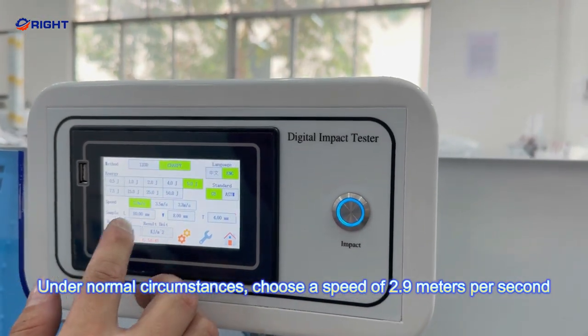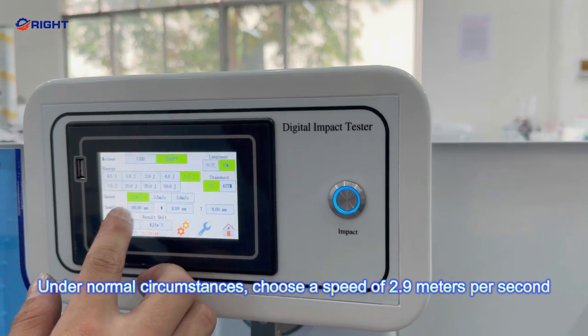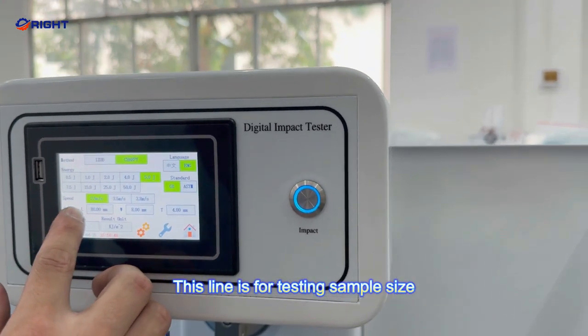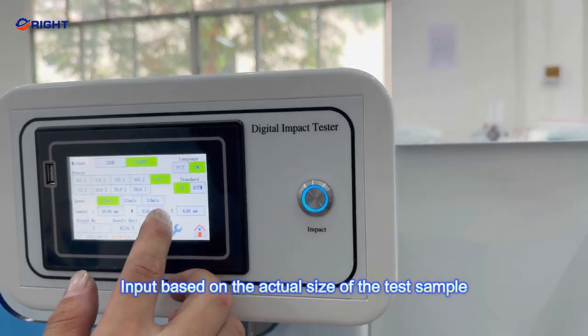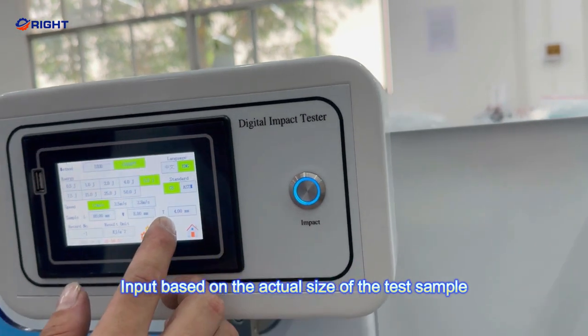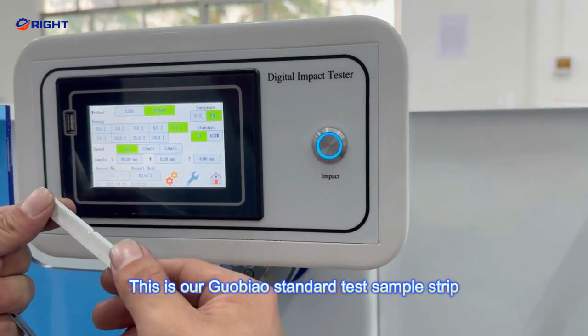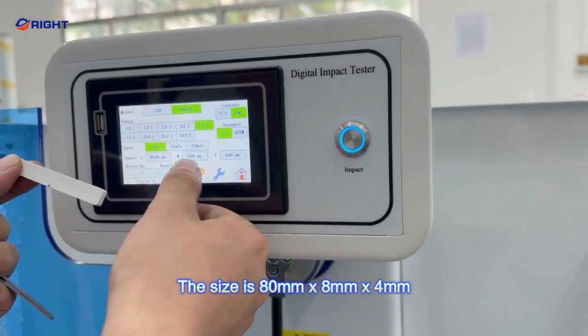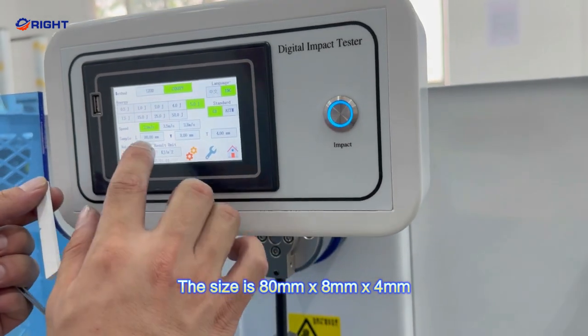Under normal circumstances, choose a speed of 2.9 meters per second. This line is for testing sample size. Input based on the actual size of the test sample. This is our Guobiao standard test sample strip. The size is 80 mm x 8 mm x 4 mm.